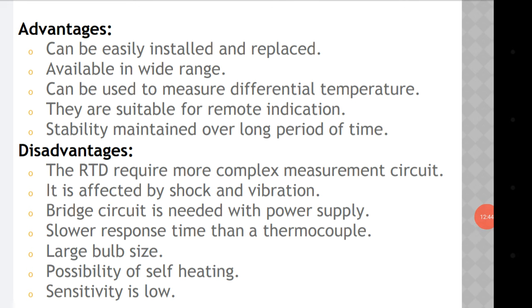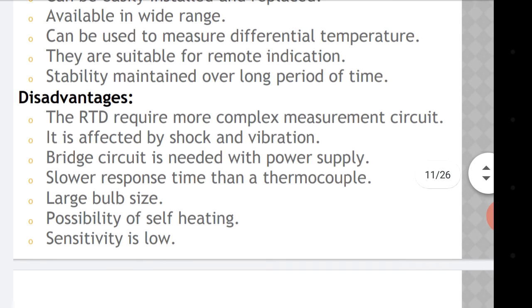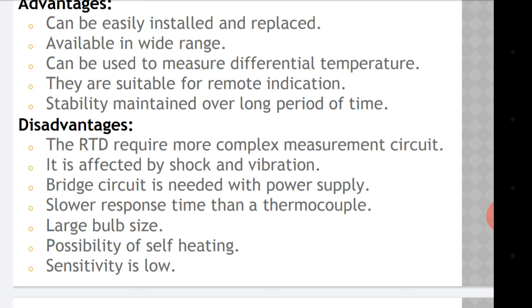What are the advantages of RTD? It can be easily installed and replaced. It is available in a wide range. It can be used to measure differential temperature. They are suitable for remote indications. Stability is maintained over a long period of time. Now for the disadvantages: RTD requires a more complex measurement circuit, and it is affected by shock and vibrations — so if the device being measured is experiencing vibrations, the output of RTD may not be proper.